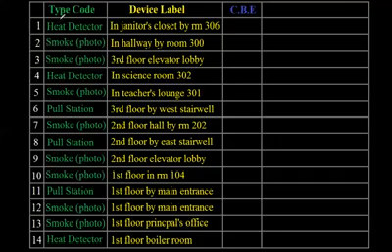It cares about this device number. It cares about the heat detector, and then we'll give it a label, and that's more for the human interaction with the panel. If it were a fireman coming in to figure out where the alarm was, that's for them. Or if it was somebody trying to troubleshoot a problem, that's for us. The panel doesn't care that device 1 is in a janitor's closet by room 306. It's not going to check the janitor's closet in room 306. It's going to check for device 1. So I could label this whatever I want, and it's only to help guide a user to that device.